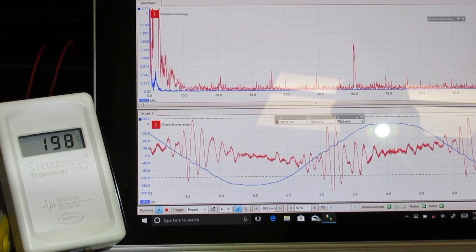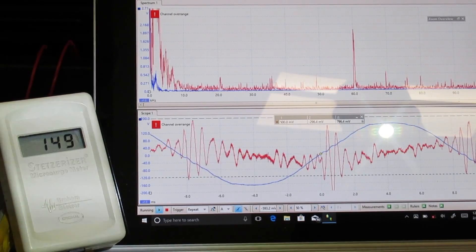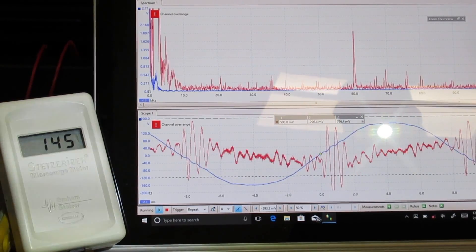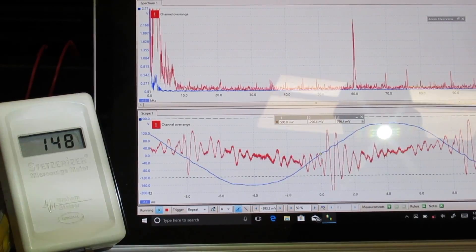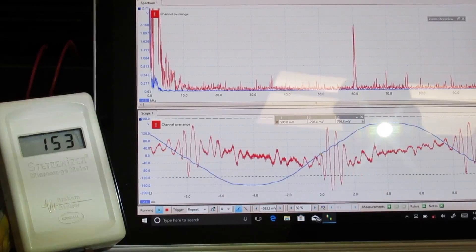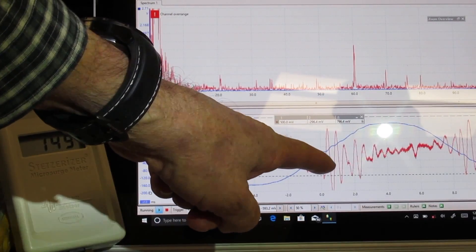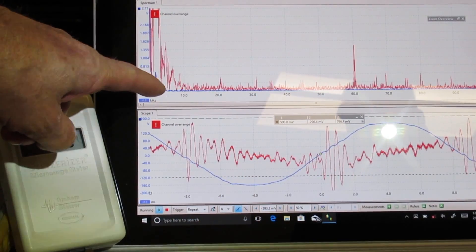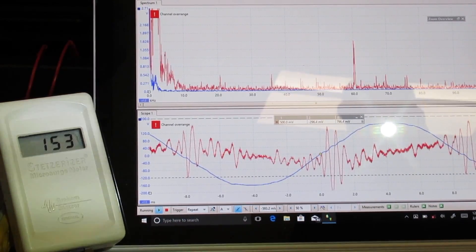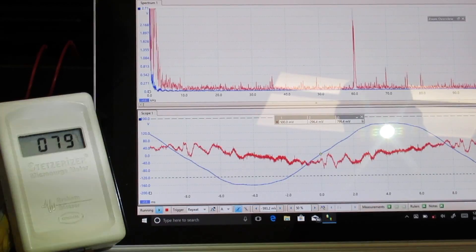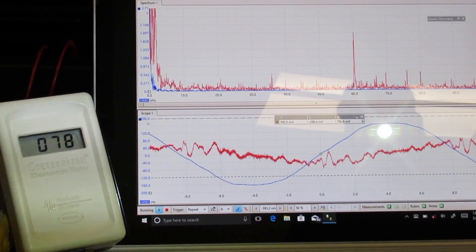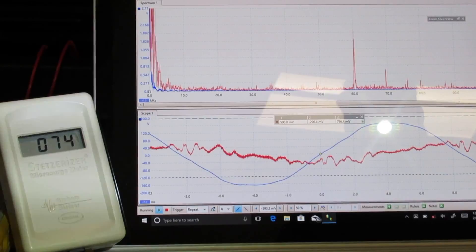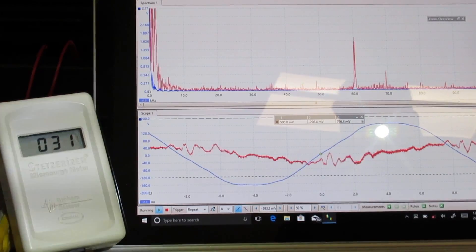Now we're going to use the same 100 amp DNA line filter, but we're going to switch to the low-frequency model. And you can see the low-frequency model cleans up a lot of these frequencies here, and that's down here in the below 5 kilohertz range. So the low-frequency model gets us down to 77, and with the Stetser filter, it gets us down to 33.